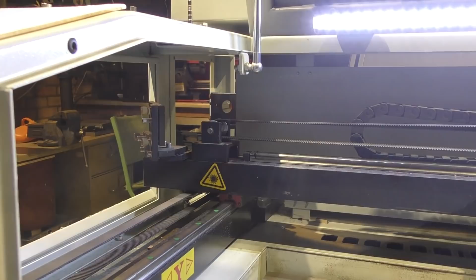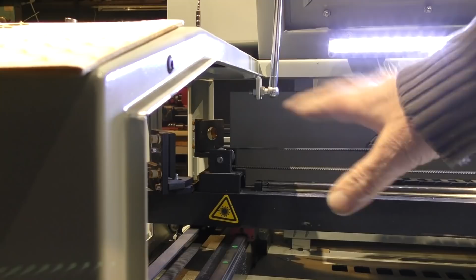Now, it's probably going to take more time cleaning your mirrors and reconditioning them if you have to, than it will to actually align the beam. Beam alignment is actually a very simple process. There are 2 very simple stages and 1 more complex stage. So let's take the very simple stages to start with. Now, I can't show you mirror 1 from the back of the machine because it's just not the right angle to show you what's going on.